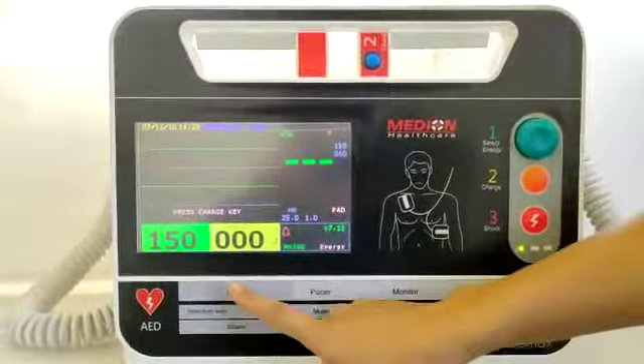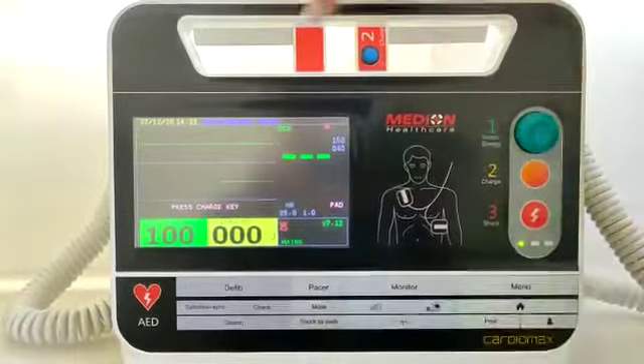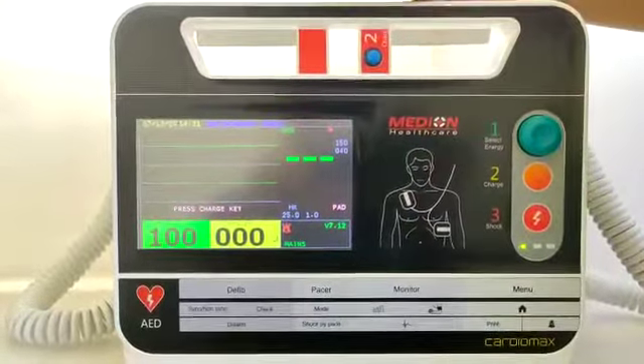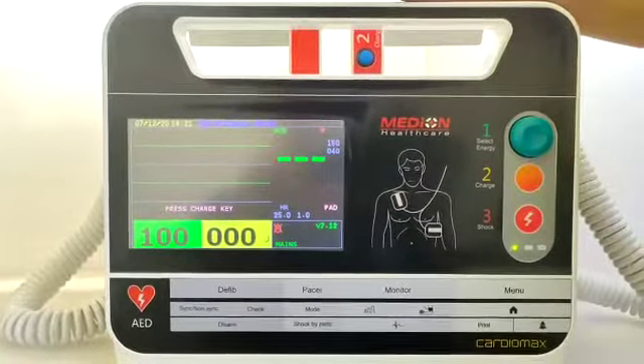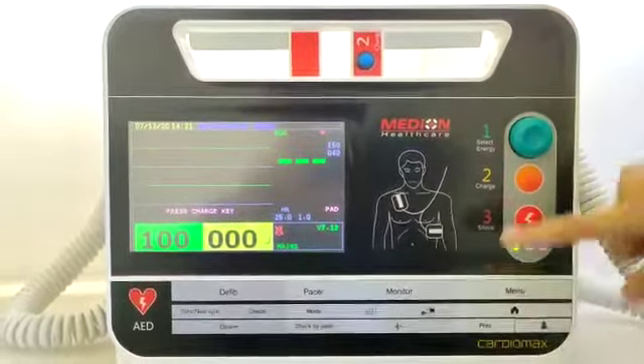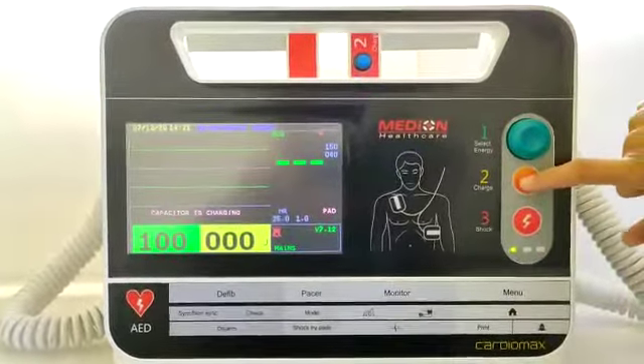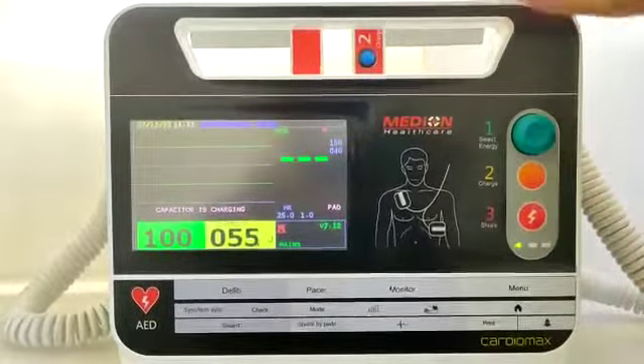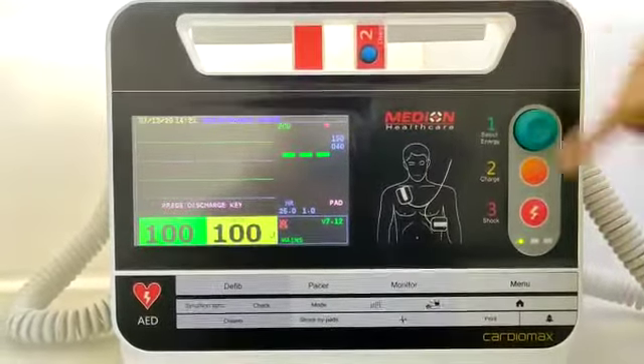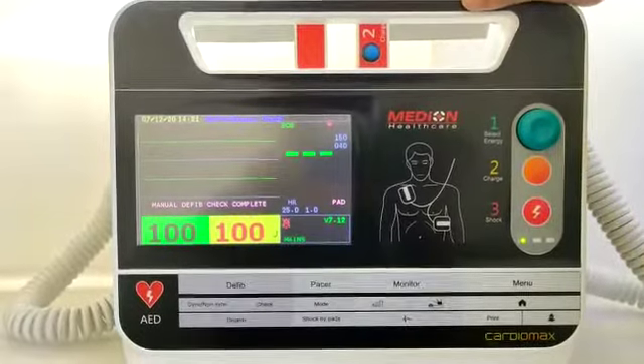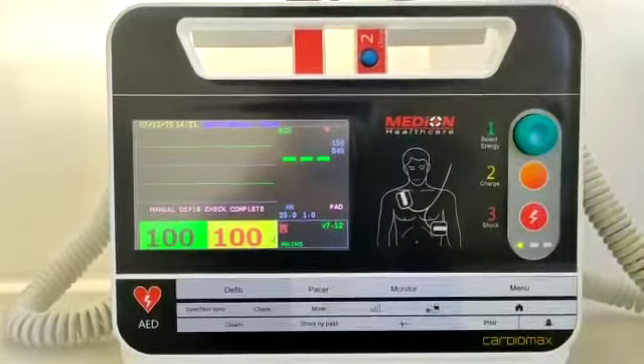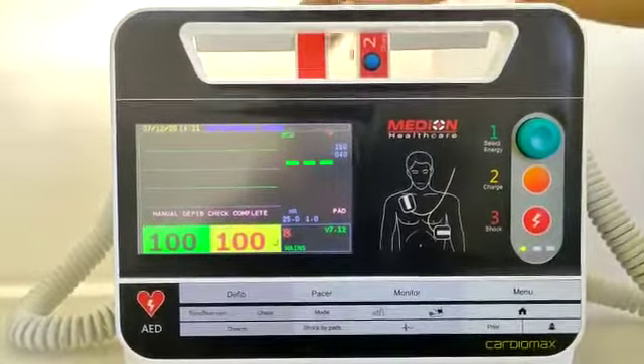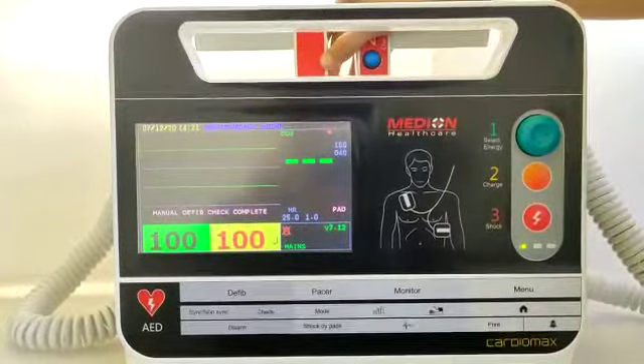Next is the defib check mode. Defib manual check mode is used to check the performance of the defibrillator. So a user can charge from here and deliver a shock. Also, the user can use these paddles to charge and discharge, but make sure these paddles are connected in the cradles.